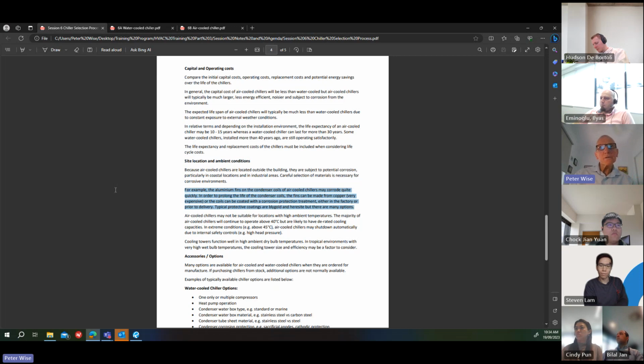So on an air-cooled chiller, for example, the aluminium fins on the condenser coils may corrode quickly. You've got different metals. You've got the copper tubes and aluminium fins on the condenser coils. Differential metals set up corrosion cells. Now, if you've studied a bit of corrosion, you'll understand how that works, the electrolytic process. And because they're outside, they're going to get moisture on them, which encourages this corrosion process to occur, particularly if there's salt or acid in the air.